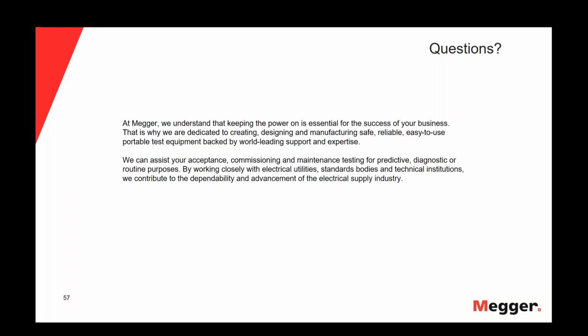The IEC standards, so this is how it works. IEC itself does not have a dedicated VLF standard. It has all kinds of apparatus standards and test practices standards, and there's one for high voltage testing. This standard, IEC 60060, also contains cable testing after laying installation, and it will refer you to a regional standard, which in this case is CENELEC. And CENELEC has two parts that are relevant for this, HD 620 and 621 S1, that's the full length, and that contains the test parameters for VLF testing. In line with this is the German VDE 0276, which is the VLF standard for Germany, where all of this actually originates.